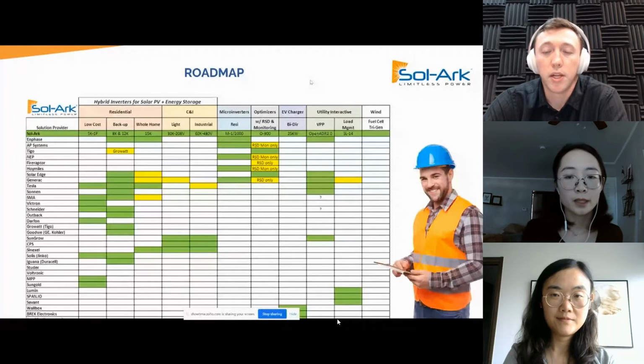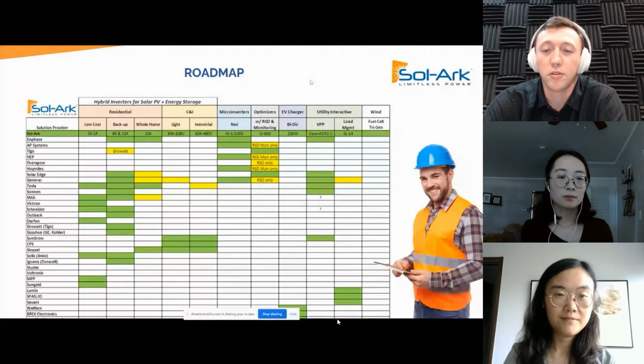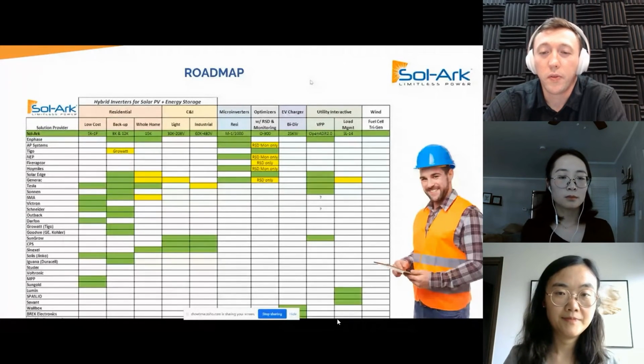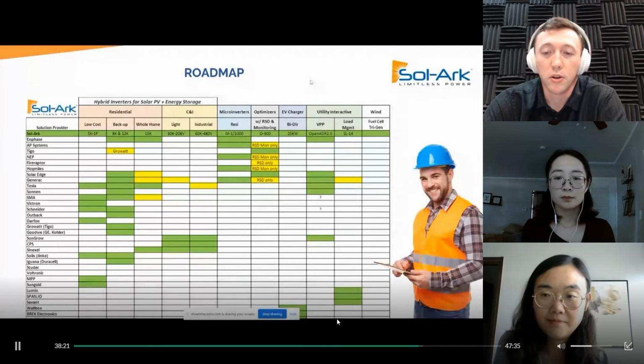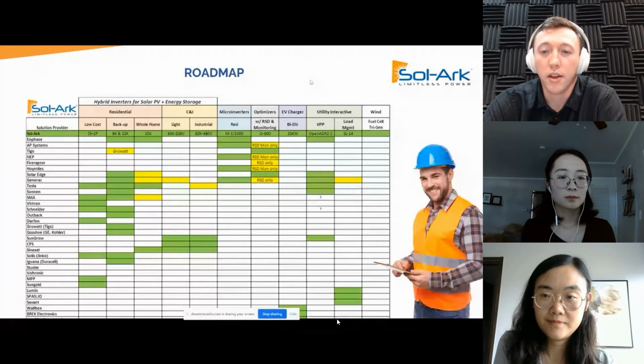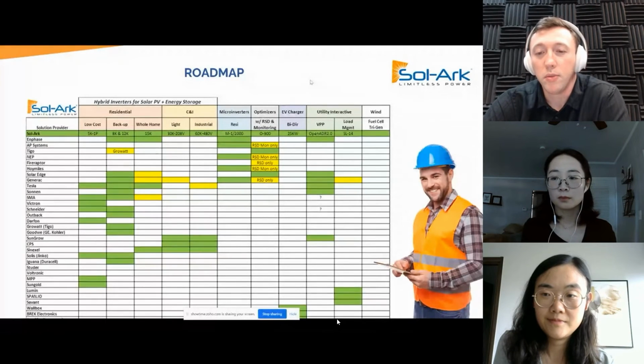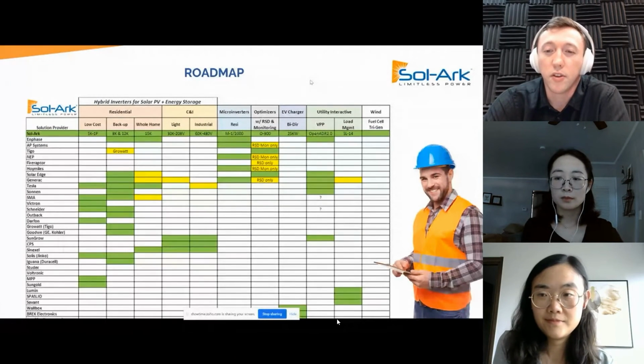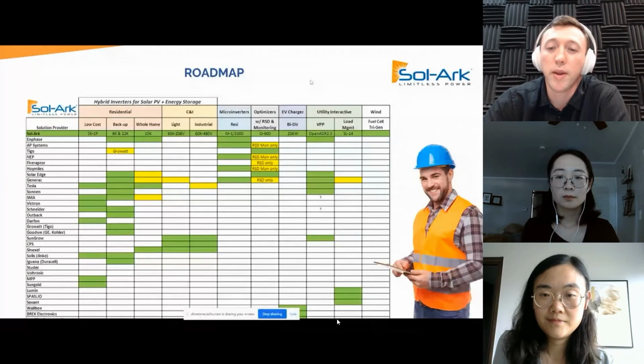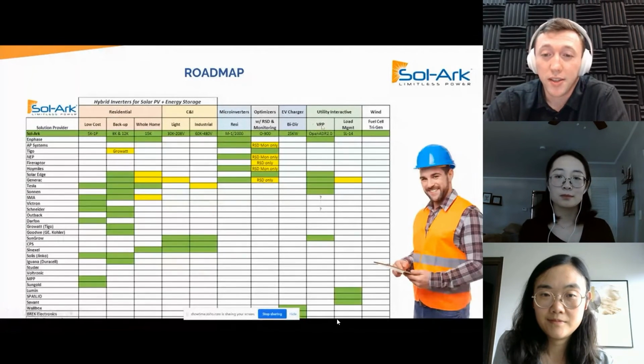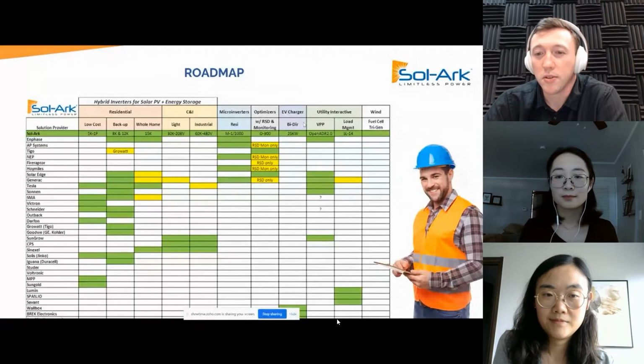And a quick explanation on what that is: basically the utility is borrowing from homeowners' battery banks, discharging it to offset peak hours. Those programs are going to be implemented through aggregate communications called OpenADR 2.0 or IEEE 2030.5. We're looking to acquire both those communication standards for our inverters so we can easily tie into future VPP programs with other utilities once they roll them out. And the advantage of doing that is that the utility is going to cut the homeowner a nice check depending on what they agree upon. So it's going to be a bit better than your average net metering scenario.